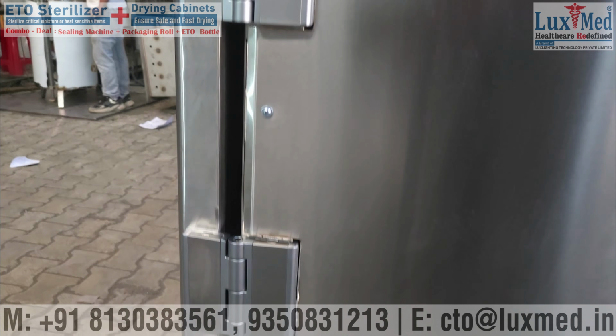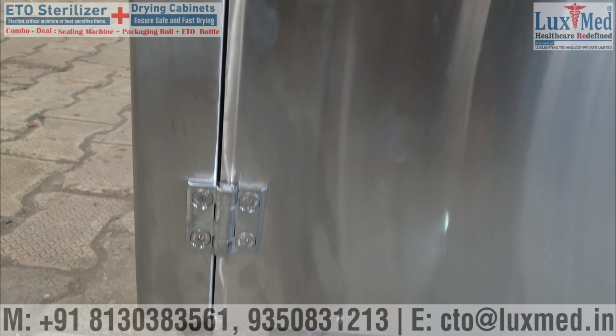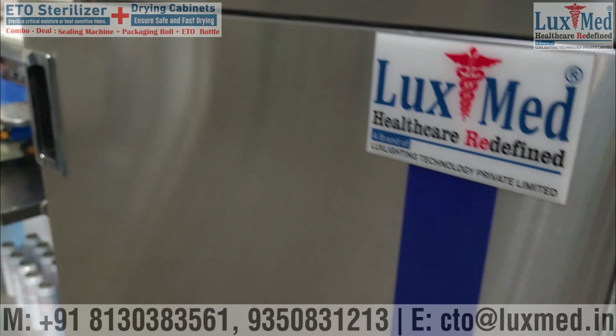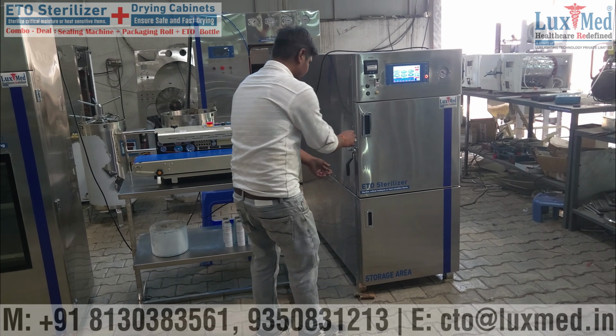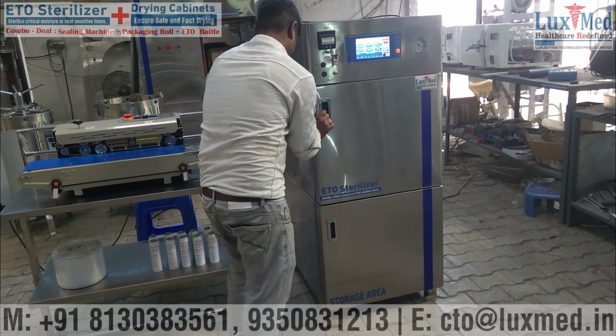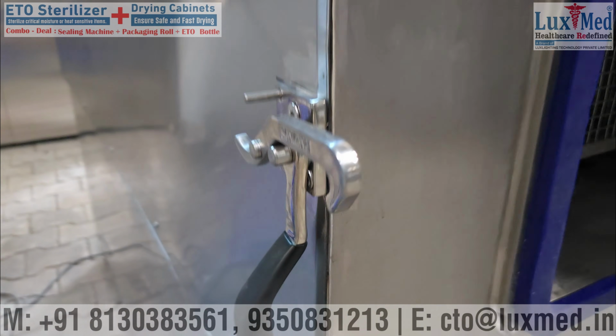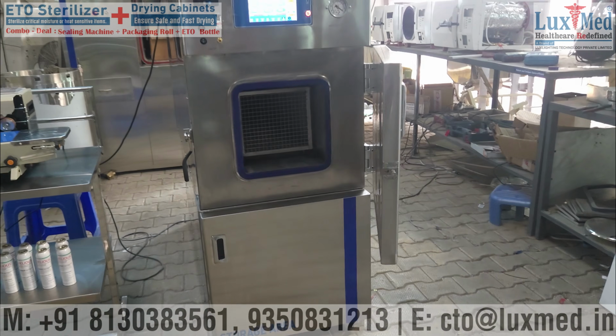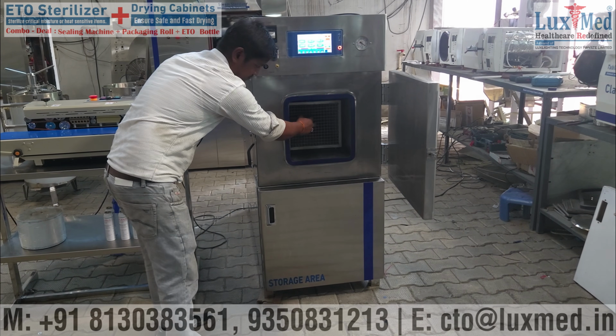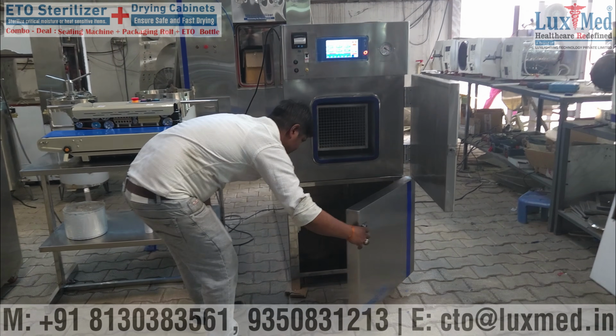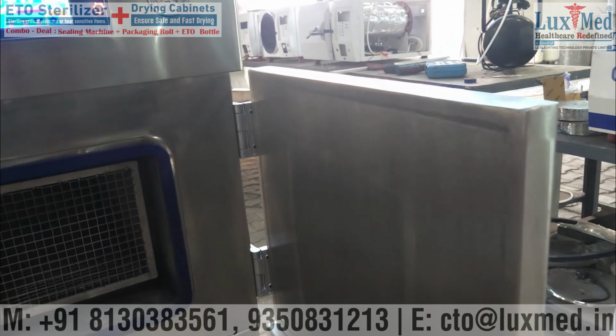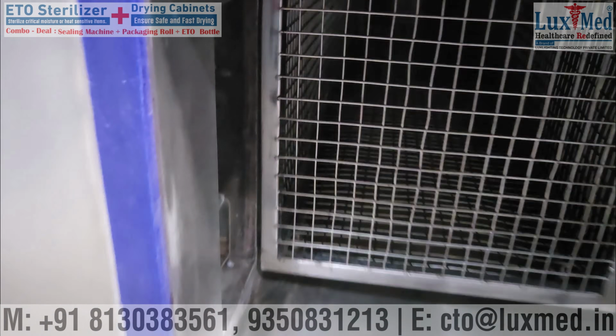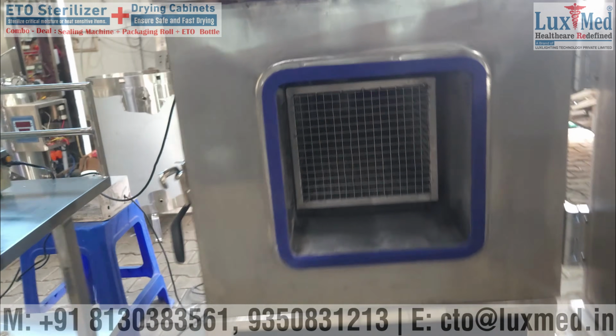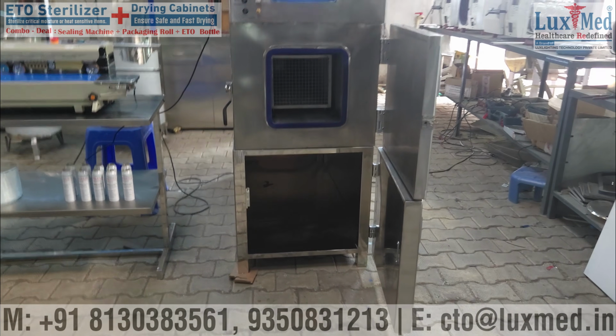Typical specifications. Primary use: microbial sterilization of heat-sensitive devices. Drying cabinet: moisture removal from instruments and labware. ETO sterilizer, temperature: low temperature, 30 degrees Celsius to 60 degrees Celsius. Drying cabinet: warm to hot air circulation, 50 degrees Celsius to 120 degrees Celsius. ETO sterilizer, medium: ethylene oxide gas cartridge. Drying cabinet: forced hot air and HEPA filtration. ETO sterilizer: fully automated PLC control for gas, vacuum, and aeration. Drying cabinet: programmable drying cycles, temperature, and humidity. More advanced automation with LuxMed proprietary control system.